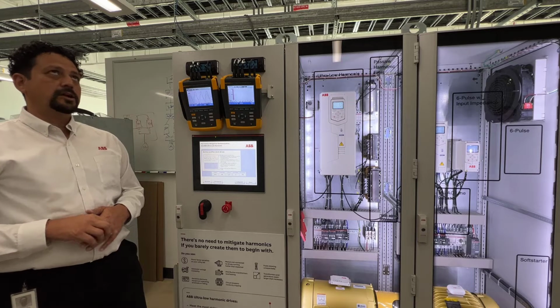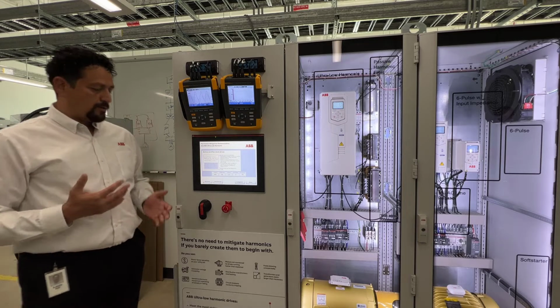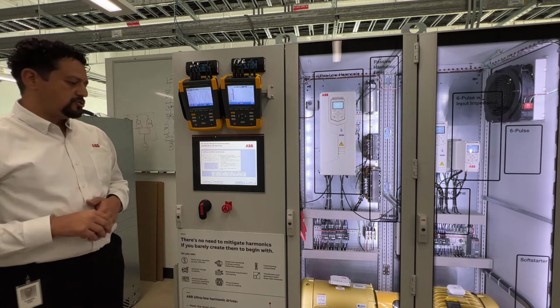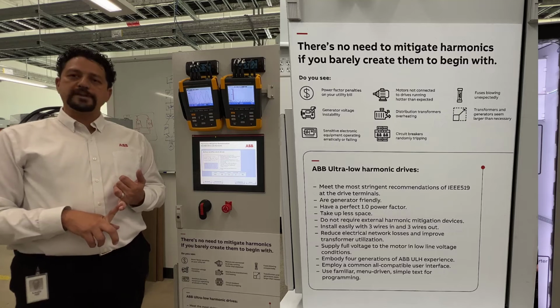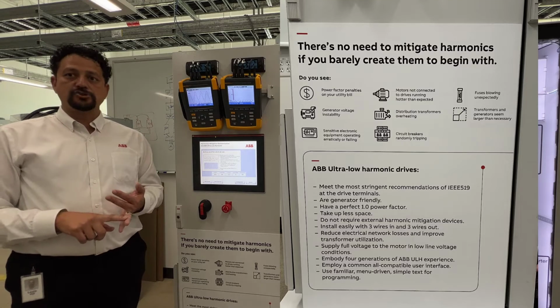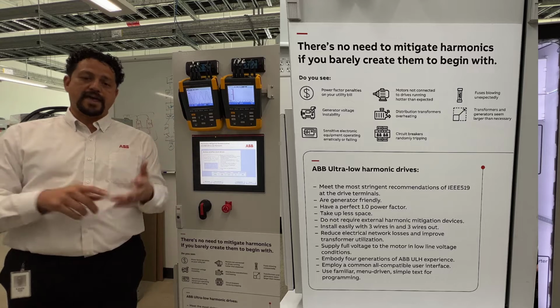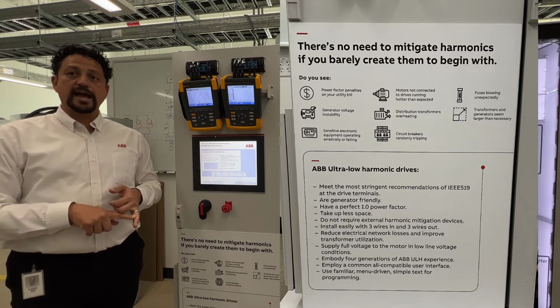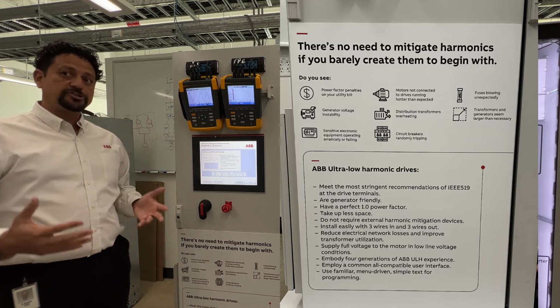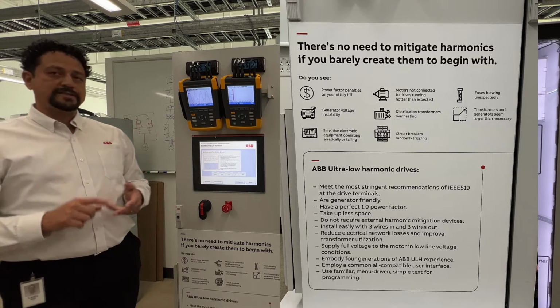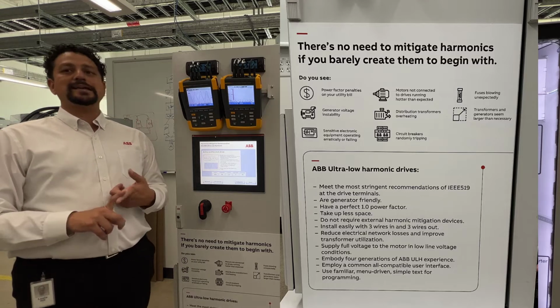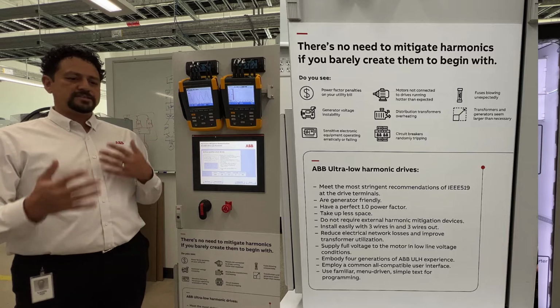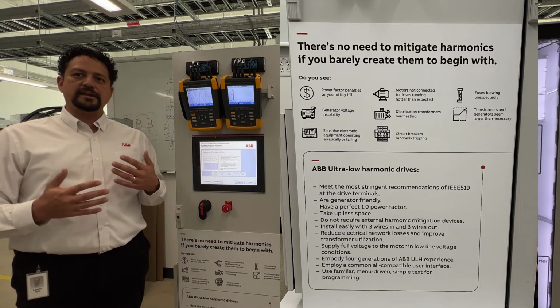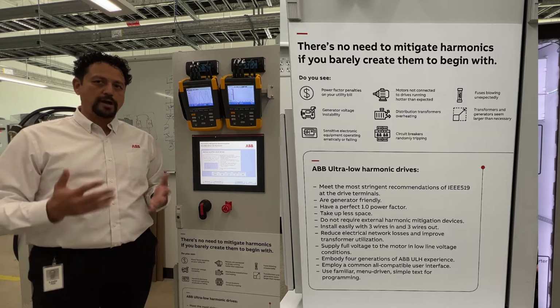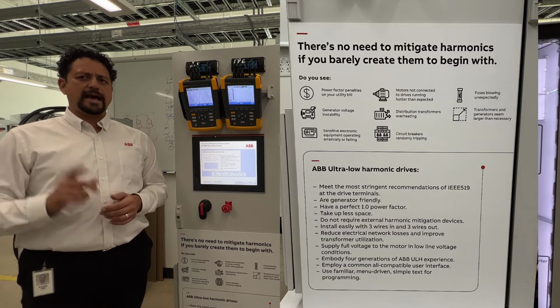When we look at why you need it, we've got a host of reasons. You might see motors tripping on over temperature because they're not on drives, and the network is so messed up that another motor running across the line might be overheating because of the voltage distortion. You might see circuit breaker trips. You might see lights flickering from time to time. These are nuisance things that you might be aware of when you're walking through your facility. You might be thinking, I might have a problem.